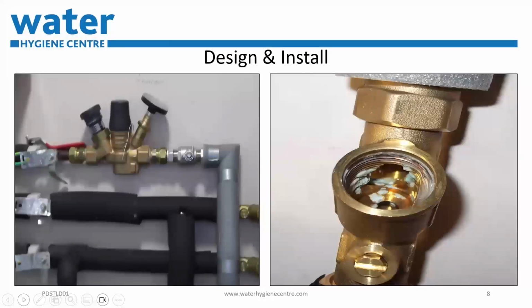And the issue really is, I suppose, if we get it right first time, as in we have the right design, we haven't got a multitude of TMVs where they're no longer required. At the end of the day, the design house who surveys and designs the system may be averse to risk of install potential, but they unfortunately may not understand the risks associated from a legionella perspective about how an excess of TMVs requires an excess of service and fail-safe strip downs, and locations for biofilm to form, and obviously behind that biofilm, waterborne pathogens can live and breathe quite nicely. Okay, next slide, please.